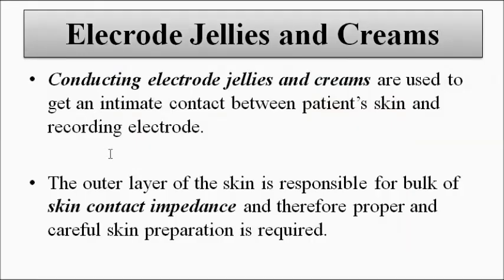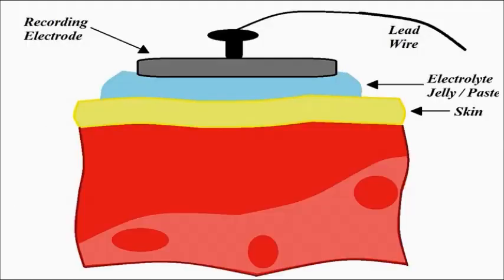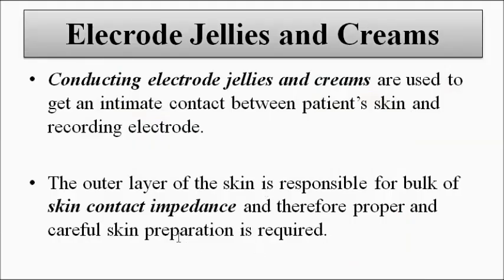Conducting electrode jellies and creams are used to establish good contact between the patient's body part or skin and the recording electrode. The extreme outer layer of the skin is responsible for a bulk or large amount of impedance, which is called skin contact impedance. Therefore, there should be proper preparation of the skin, which is called skin abrasion.